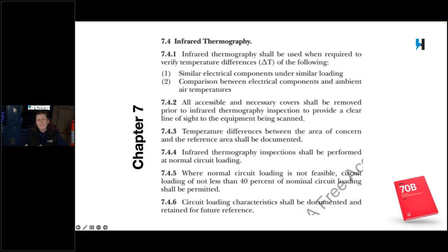If normal loading isn't feasible, say you're in an explosive or hazardous classification area where opening equipment with dust in the air is more hazardous, that's where we look to 7.4.5: if normal circuit loading is not feasible, circuit loading of not less than 40% can be permitted. You still want it running, maybe just the motors, which could be about 40% of normal load or a bit higher depending on what you're processing. There are ways around this.